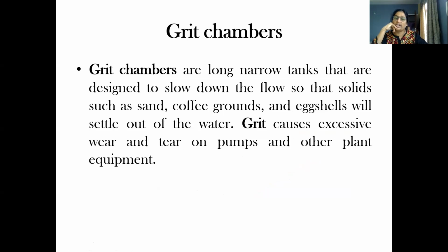Grit chambers are long, narrow tanks that are designed to slow down the flow so that solids such as sand, coffee grounds, and eggshells will settle out of the water. And grit causes excessive wear and tear on pumps and other plant equipment. So the inorganic particles like eggshells, coffee grounds, sand, broken stones, pebbles, and metal pieces, these are the grits.